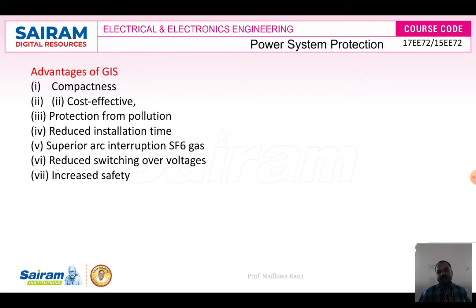A gas insulated substation is compact, and it will be very small. If you are using air, we need an air compressor, which is large equipment in a substation, and it also gives more noise. But if you use SF6 gas, there is no need for an air compressor. The advantages are compactness, cost effectiveness, protection from pollution, reduced installation time, superior arc interruption by SF6 gas, reduced switching overvoltages, and increased safety. So these are the seven advantages.